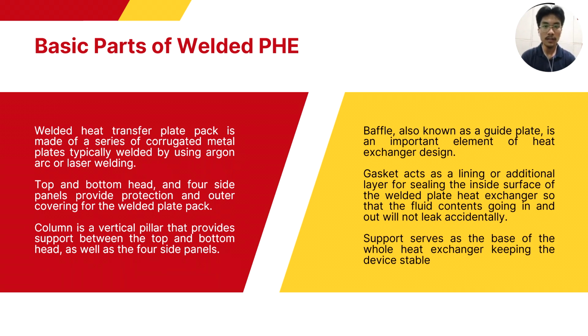Next, top and bottom head and 4 side panels provide protection and outer covering for the welded plate pack. So these components are the outer covering and the protection of the interior of the welded plate heat exchanger. They are basically made of steels as well and strong metals in order to protect the interior of the equipment. Also, the top and bottom head and the 4 side panels can be detached easily and quickly by just loosening and removing the bolts. So this is really helpful for quick inspection and cleaning of the interior and the cleaning of the welded heat transfer plate pack.